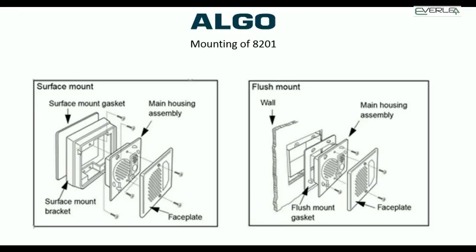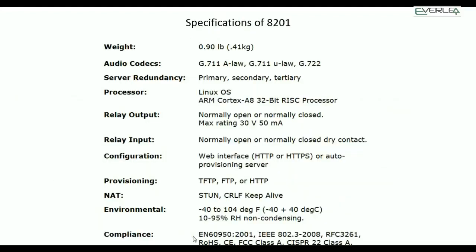Specifications: the unit weighs 0.4kg. Audio codecs supported are G.711a, G.711u, and G.722. It has server redundancy for primary and secondary — if your main voice server fails, the Algo 8201 will roll over to the secondary. It runs a Linux-based operating system. The relay output is normally open or normally closed, with a maximum rating of 30 volts and 50 milliamps.